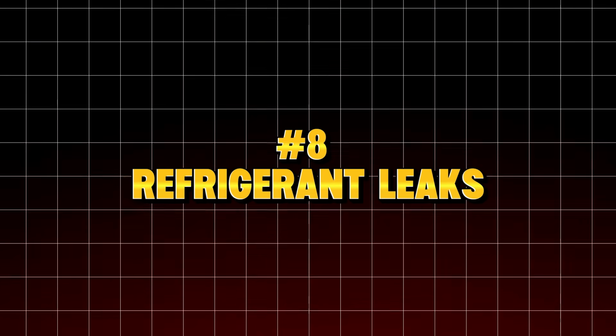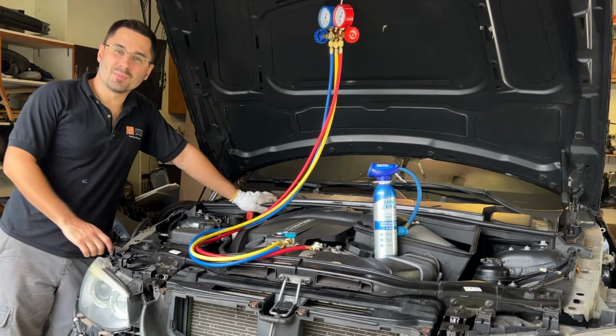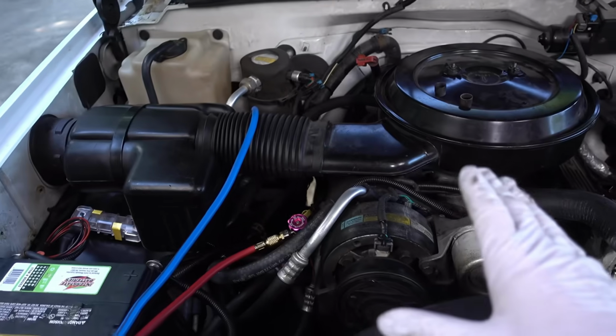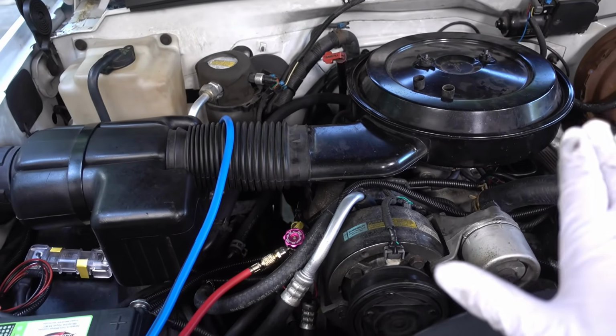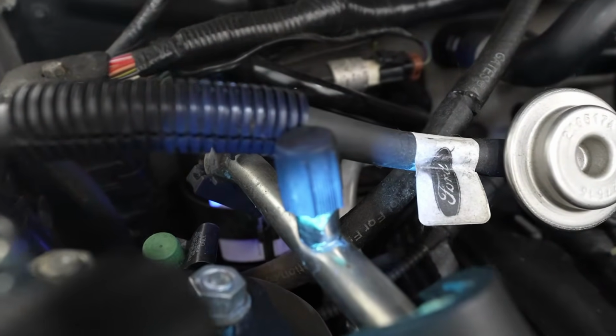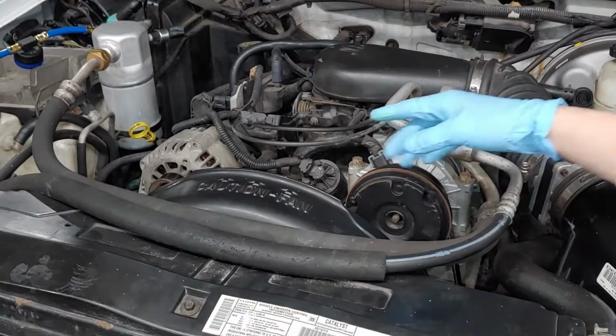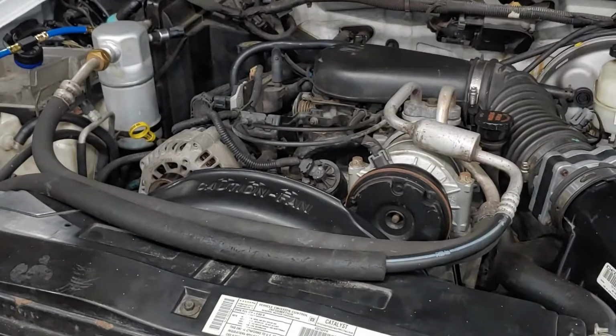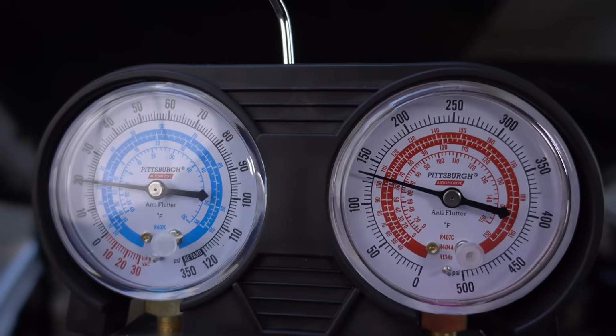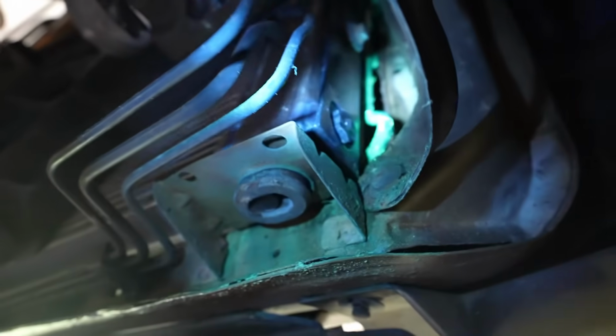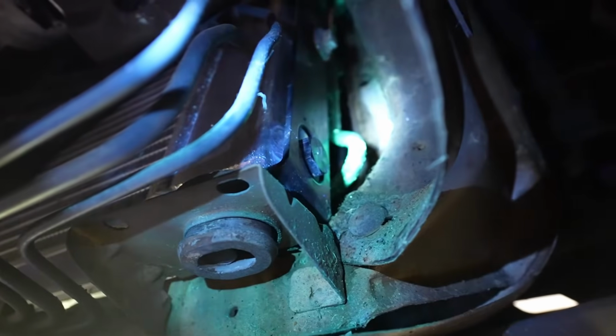Number 8. Refrigerant leaks. If your AC worked perfectly last year but barely cools this summer, a slow refrigerant leak is very likely. Many leaks develop gradually. O-rings harden, compressor seals wear, condenser tubes crack after years of vibration. Small leaks slowly reduce refrigerant pressure over months. I've found leaks using UV dye, electronic leak detectors, and pressure testing. Many are minor. Some O-ring repairs cost under $100.